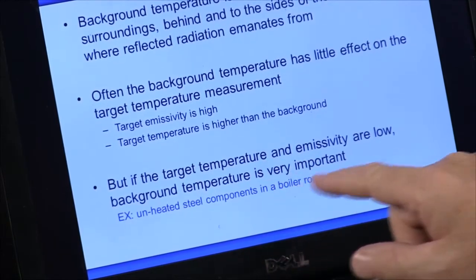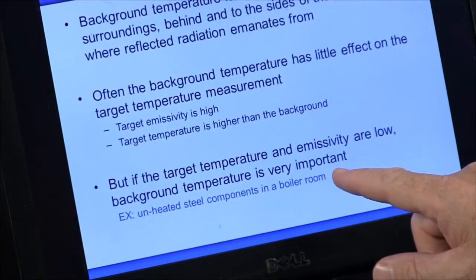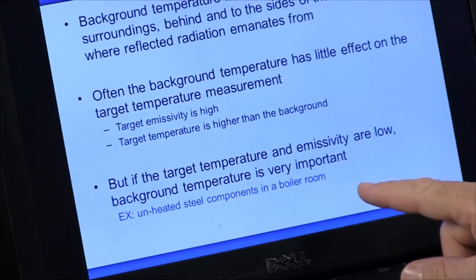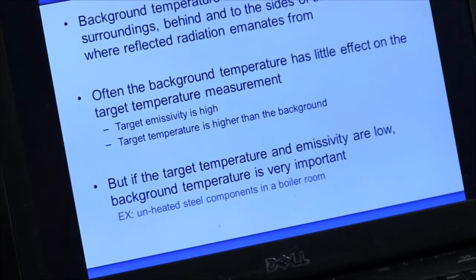But if you're in an area where the temperature difference is very low and the emissivity is low, then the background temperature can be important. For example, if you're in a boiler room and you're taking an image of an electrical connection with a hot boiler behind you.